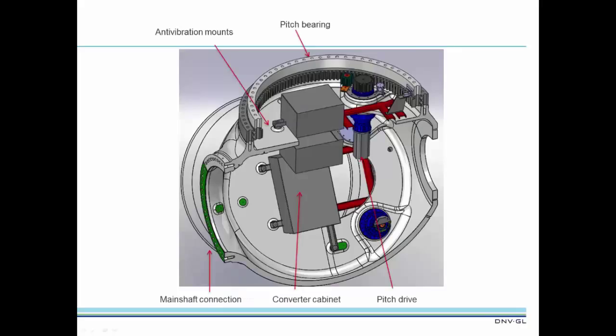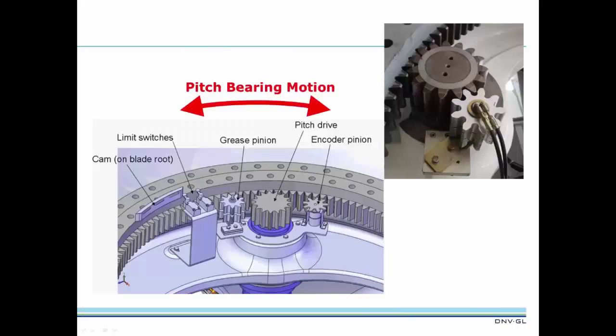The usual way to pitch the blades is to use motors called pitch actuators, or pitch drives, located in the hub of the turbine. These pitch actuators turn the blades by powering a pinion, which rotates the blade root pitch bearing. In some turbines, hydraulic pitch actuators are used rather than motors.